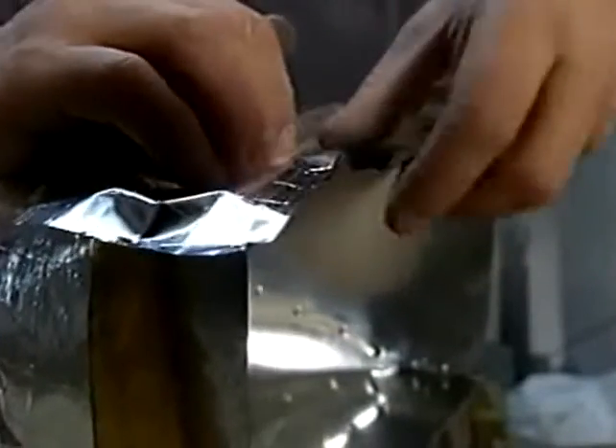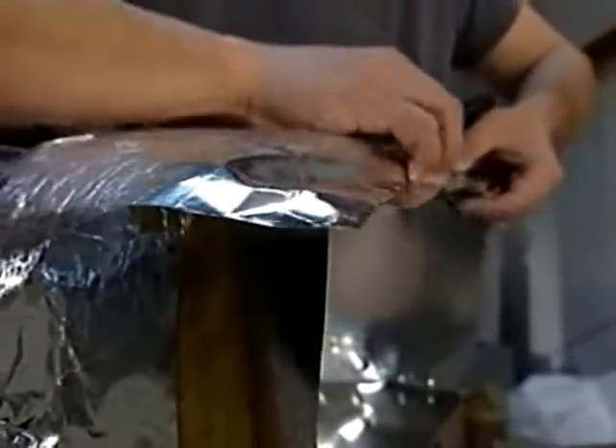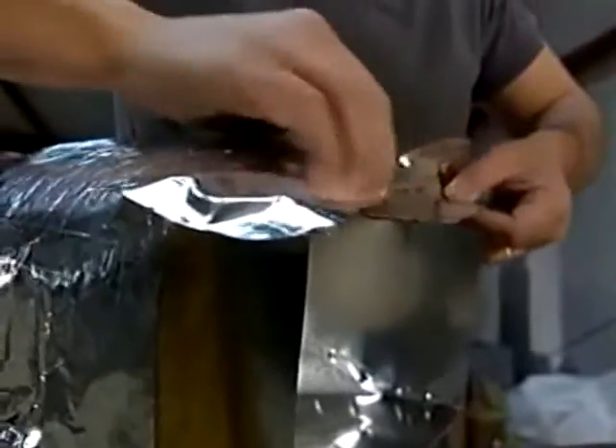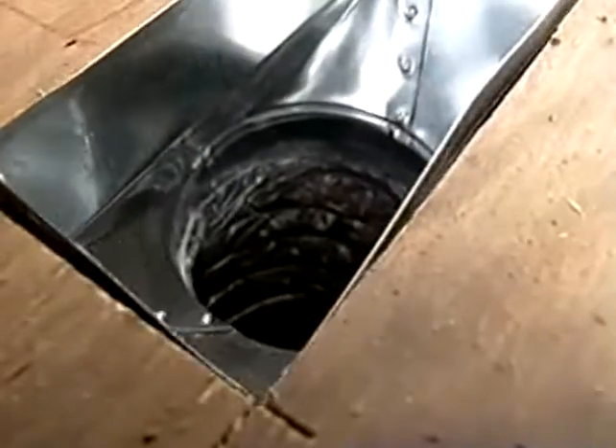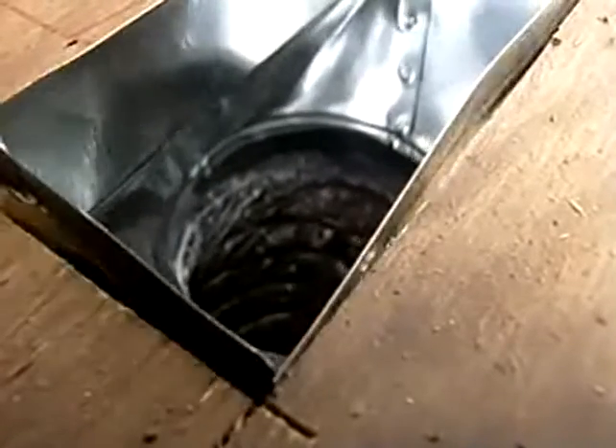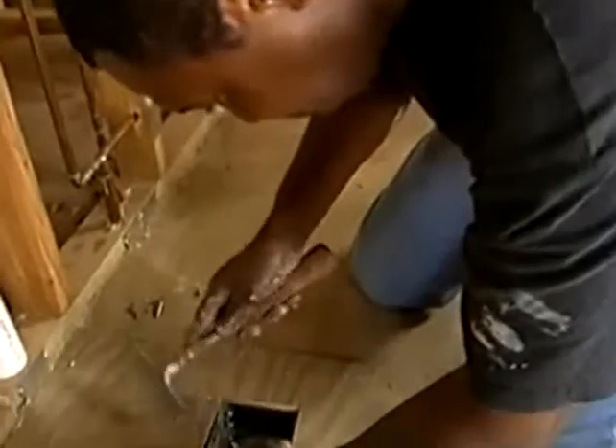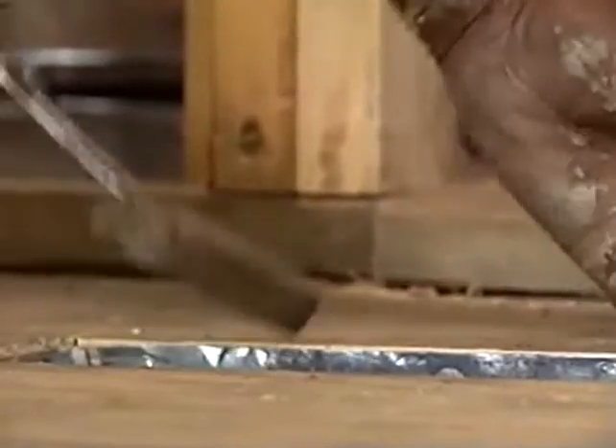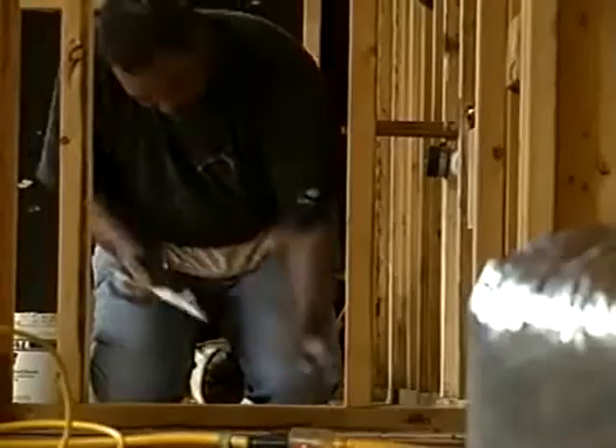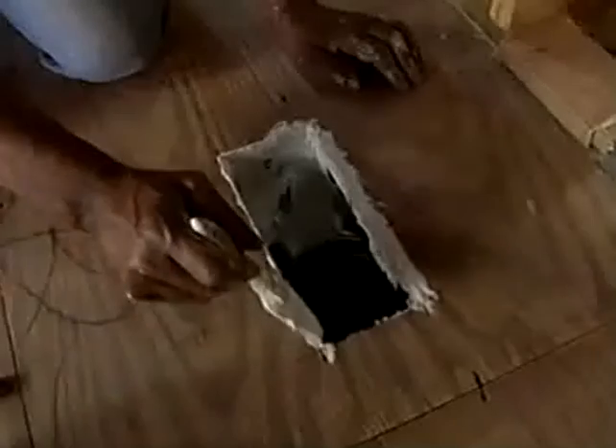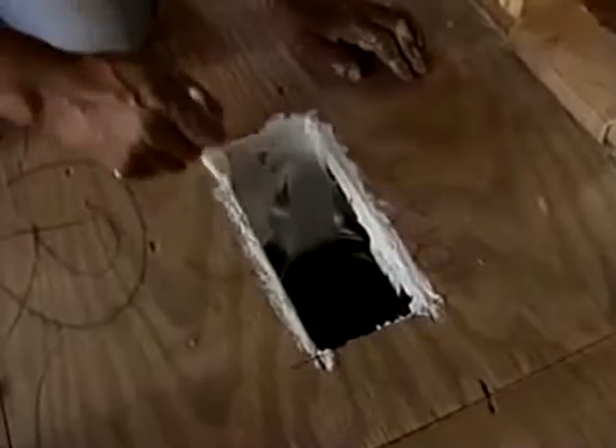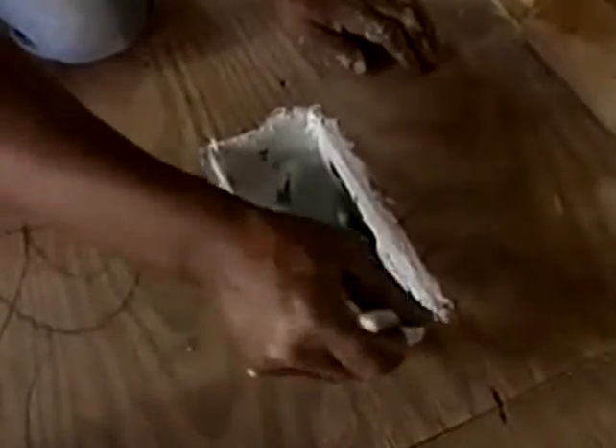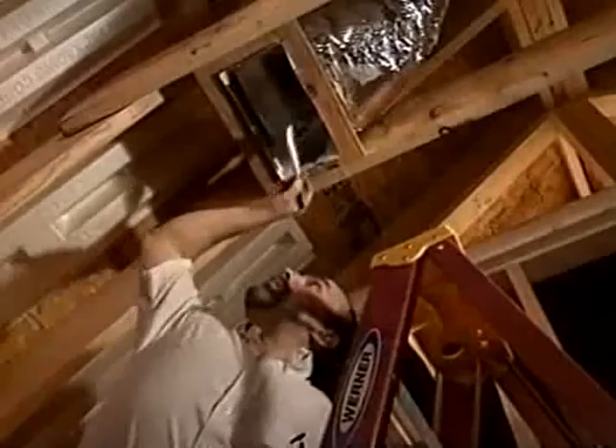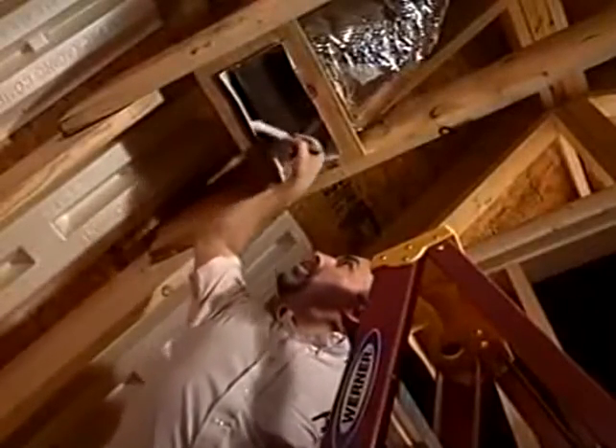Notice, he leaves a small portion at the top of the boot, which will give him just enough clearance to attach it to the subfloor. When the boot is attached to the subfloor, it is nailed into place using the traditional installation method. However, once it is secured, all the joints in the boot are sealed with mastic. Every nail hole, every small gap, including the gap between the wood and the boot, should be sealed. This same technique should be used when installing boots in ceilings.